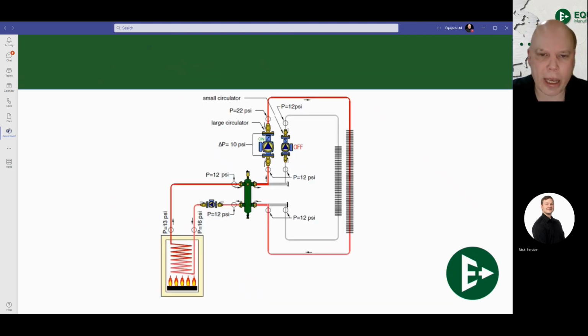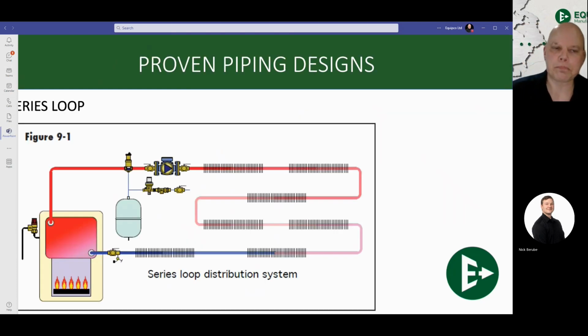A question I usually get asked is where does the expansion tank go on these. I like to see it on the suction end of my primary pump, which you'll see right underneath that 12 equals PSI sign to the bottom left of the hydro separator. That's a great place for our expansion tank to go in that sort of system.